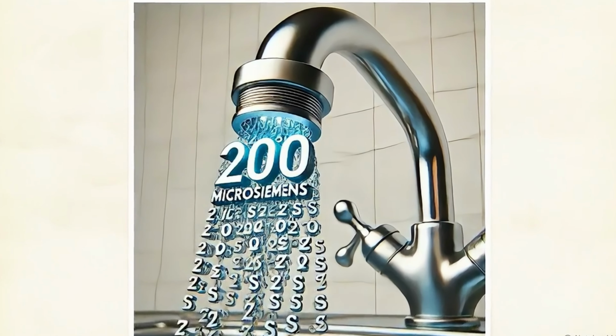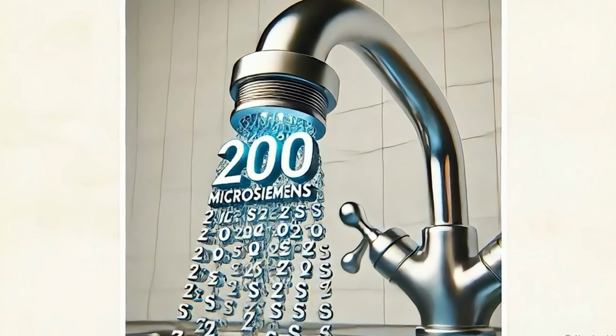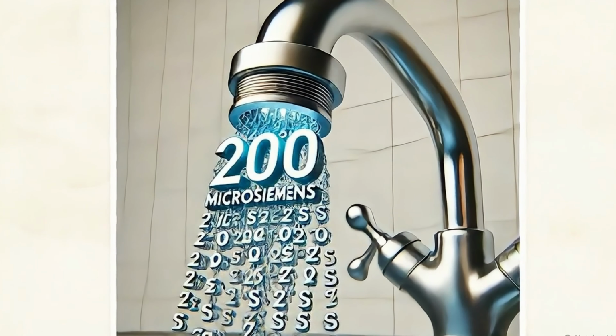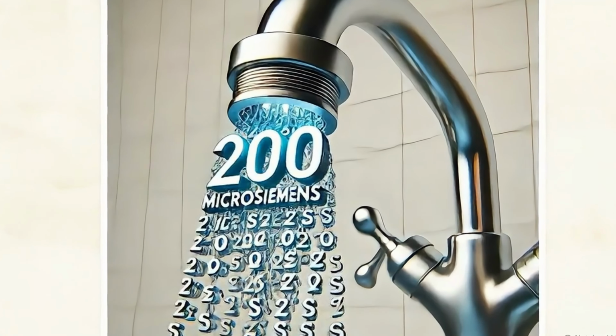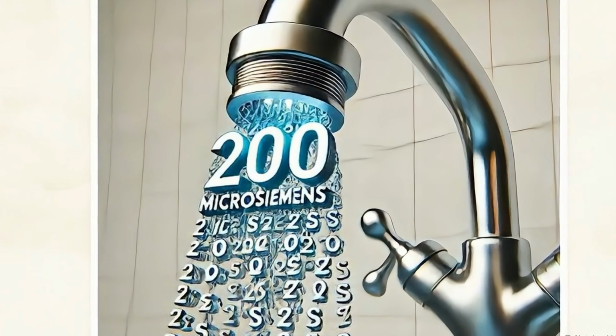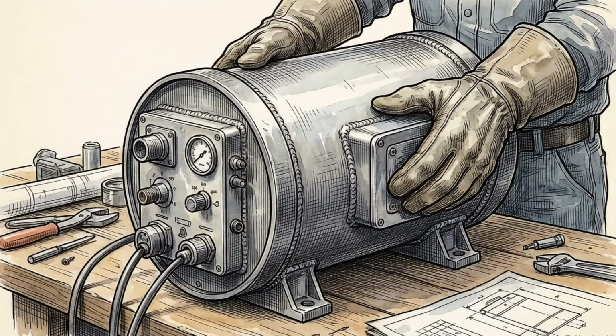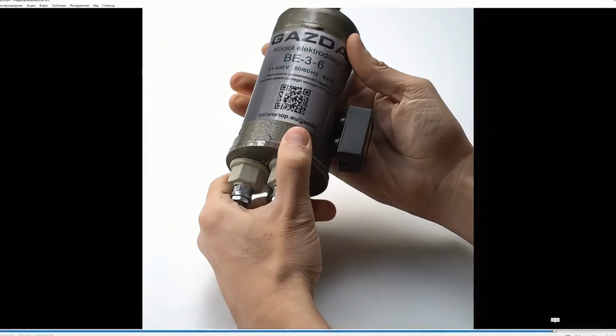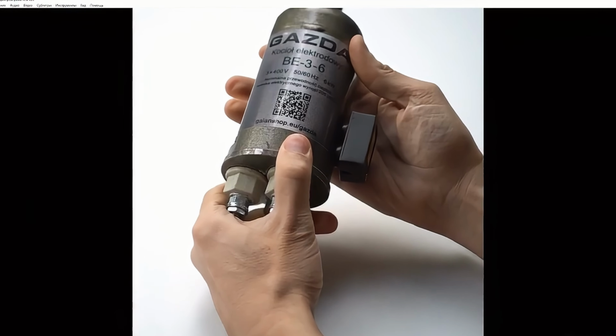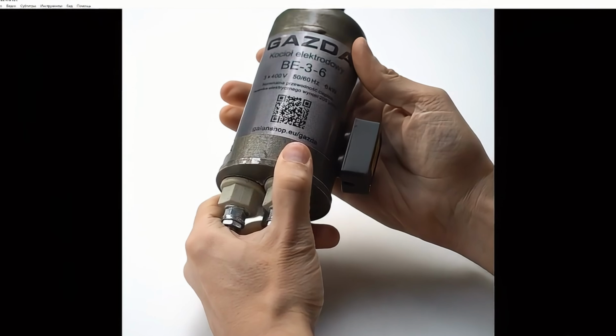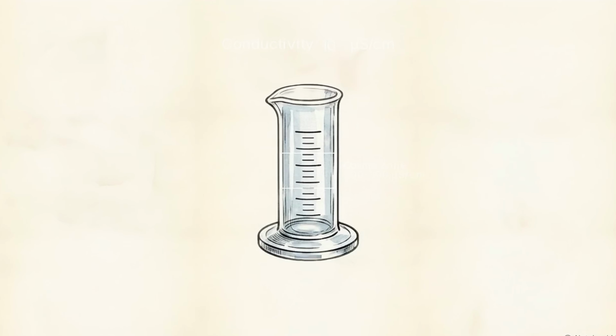Engineers measure this ionic conductivity using a specific metric, microsiemens per centimeter. This unit tells us how easily current passes through a fluid. If you look closely at the specifications for an industrial electrode boiler, you'll see a requirement right on the casing. The hardware relies entirely on the water possessing a conductivity around 200 microsiemens per centimeter. If you fill the system with distilled water, the conductivity drops to near zero and the system stalls.